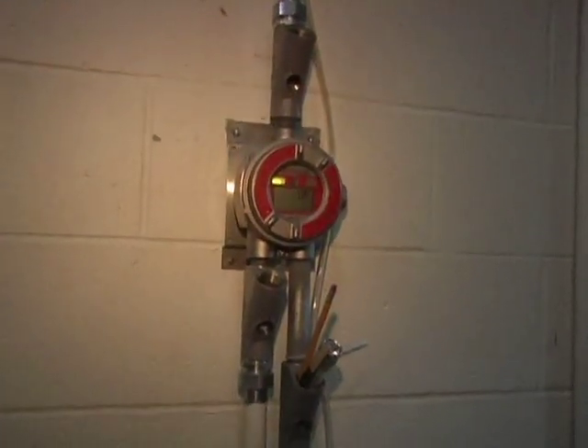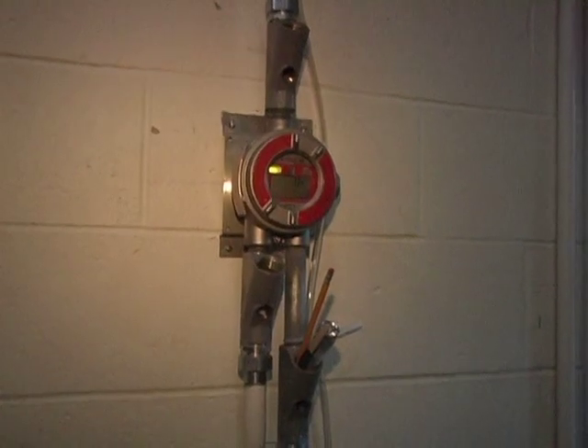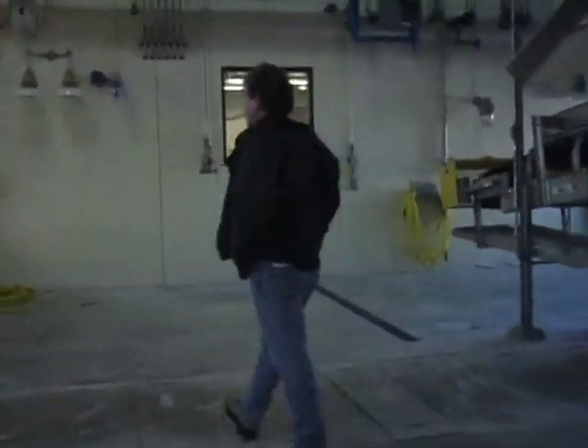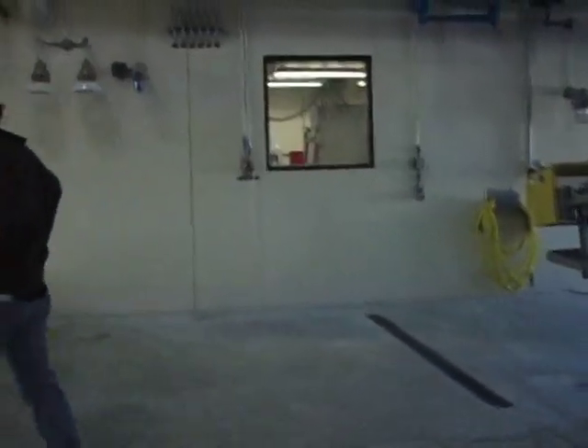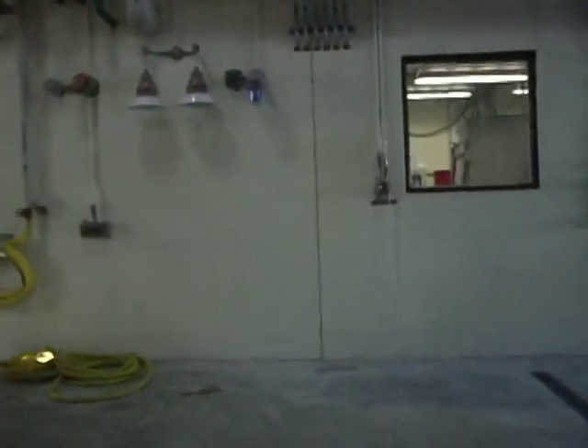Gas detection system. Located on this wall, there is a combustible gas meter that's sensing the gases at the upper portion of the building. On the opposite wall is another lower explosive limit gas detector, and then on the north and south walls there are the hydrogen sulfide meters. Any of these 4 or the 2 that are in the room next door will give you an alarm indicating that you've got a gas situation.